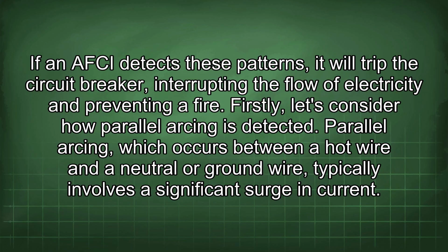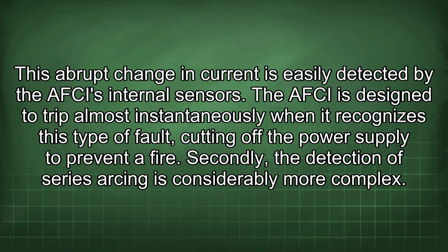Parallel arcing, which occurs between a hot wire and a neutral or ground wire, typically involves a significant surge in current. This abrupt change in current is easily detected by the AFCI's internal sensors. The AFCI is designed to trip almost instantaneously when it recognizes this type of fault, cutting off the power supply to prevent a fire. Secondly, the detection of series arcing is considerably more complex.